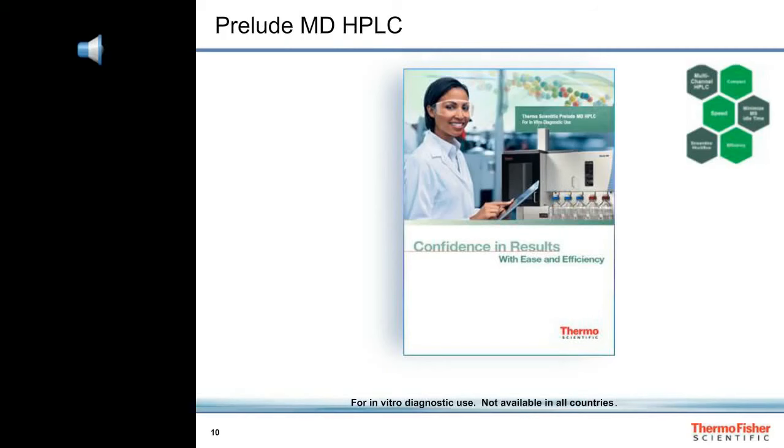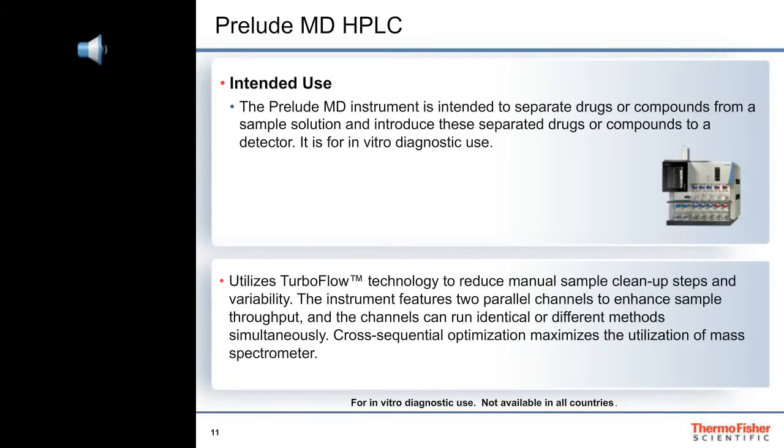Let's take a look under the hood of the Prelude MD HPLC. The Prelude MD instrument is intended to separate drugs or compounds from a sample solution and introduce these separated drugs or compounds to a detector, for in vitro diagnostic use. The Prelude MD utilizes TurboFlow technology for online sample cleanup, which replaces offline solid phase extraction. This is coupled to HPLC or UHPLC, which separates compounds of interest and elutes them to the mass spectrometer. Doing this across two channels greatly increases sample throughput for one laboratory developed test, or permits you to simultaneously run two different tests utilizing the same mass spectrometer.